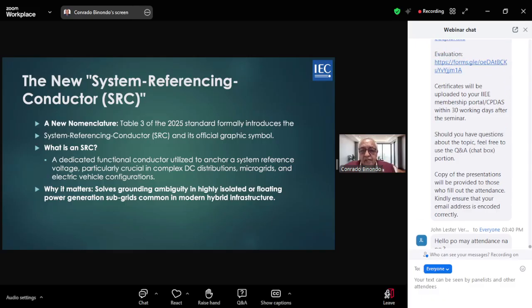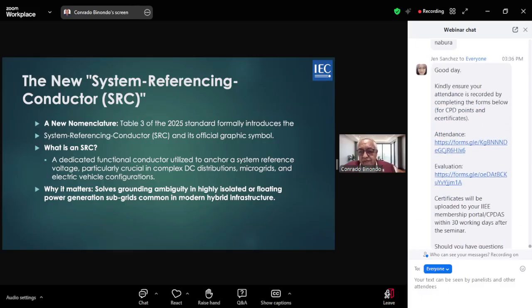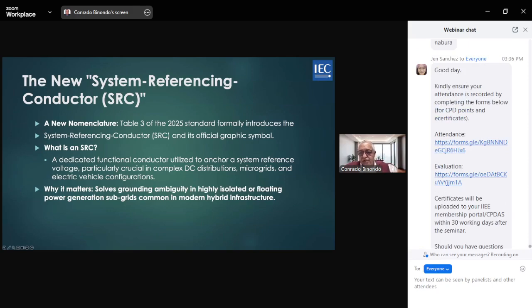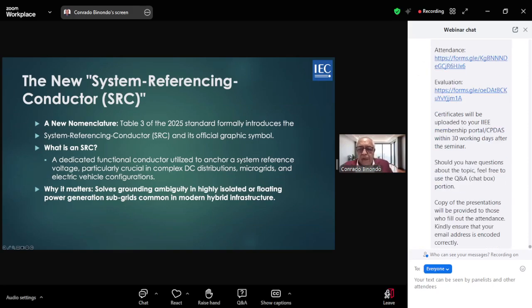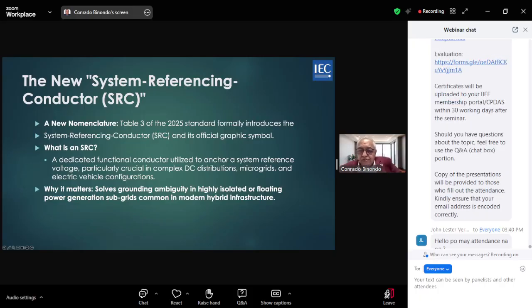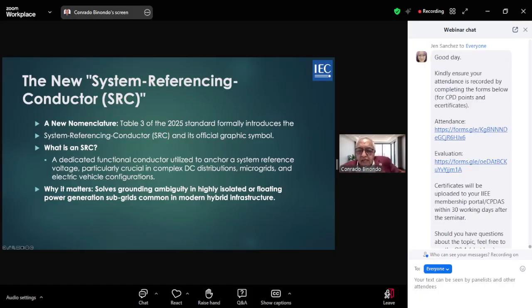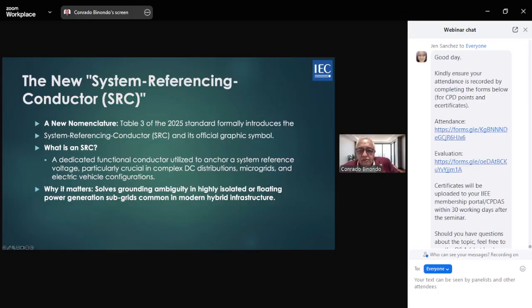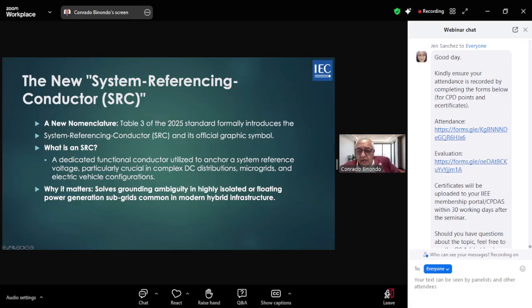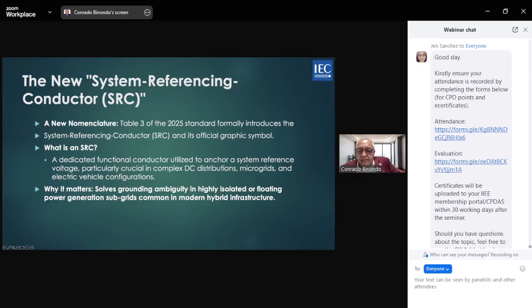Why do we need this? In advanced DC distribution networks, floating microgrids, and isolated EV charging hubs, traditional earthing references can become ambiguous. So the SRC is a functional conductor utilized specifically to anchor system reference voltage without necessarily tying it to a traditional protective earth or neutral, in the way we're used to in AC systems.